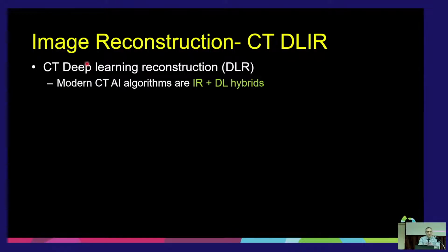All right, so iterative reconstruction, wonderful. I haven't really talked about it, but it allowed us to do a lot of wonderful things. We were able to reduce dose in a way. Basically what ended up happening is because iterative reconstruction uses an algorithm to take the noise away instead of using more photons or radiation to take away the noise, we kind of weakened or broke that link between using radiation to improve image quality. We now use an algorithm, we use mathematics to improve the image quality. It's not perfect, as we just demonstrated.